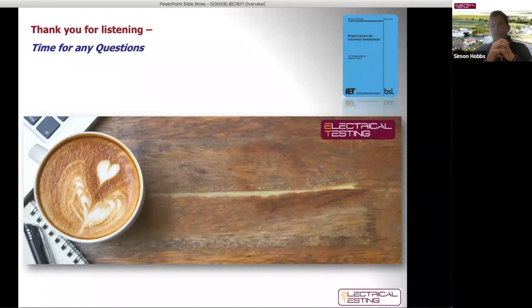Such an important subject, safe isolation. We do a lot of training with new starters, apprentices, and experienced, time-served electricians, and time and time again, safe isolation is just not understood properly. Behaviour means it's not done properly, and ultimately it's the thing that kills. Electric shock is one of the biggest things that kills. So it's really important, and is covered in BS 7671 itself, and also extensively in the guidance notes that go with it. There's a whole range of guidance notes as well.